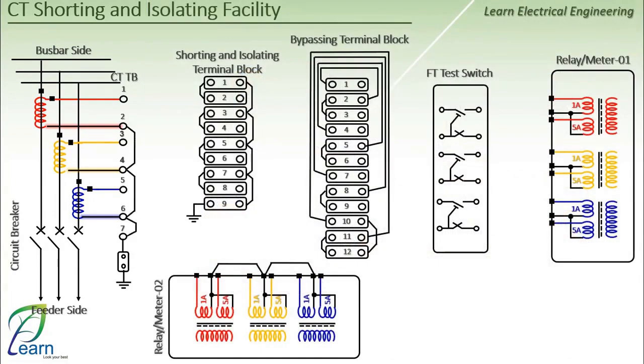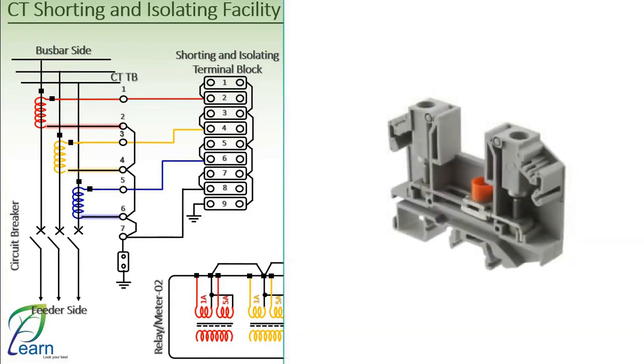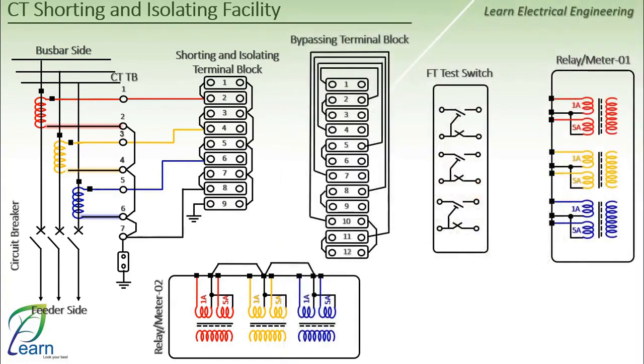After that, I exit with 3-phase and neutral from the LCC to the protection panel or metering panel and enter the slide link TB of the OTA6T type. This is the terminal block responsible for the shorting and isolating process. We notice here that each phase has only 2 terminal blocks, unlike the function we explained in the previous lecture, which now appears on the screen. If you haven't watched the lecture before, please follow it immediately.